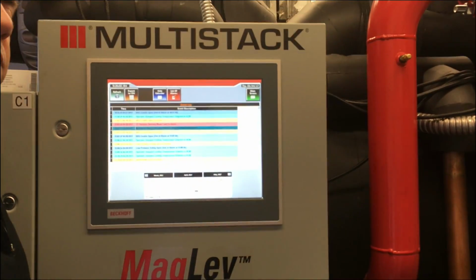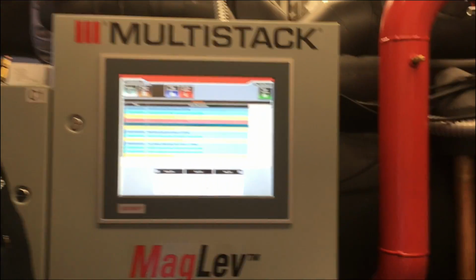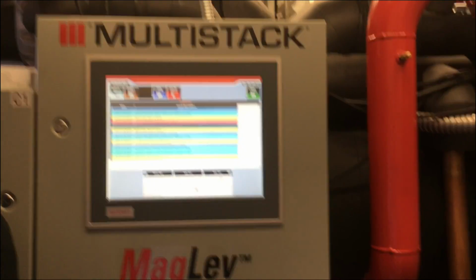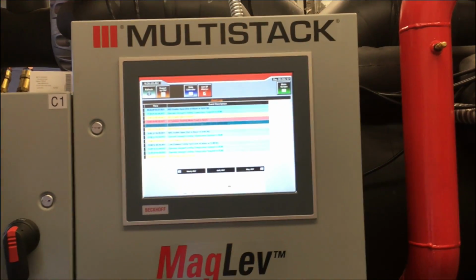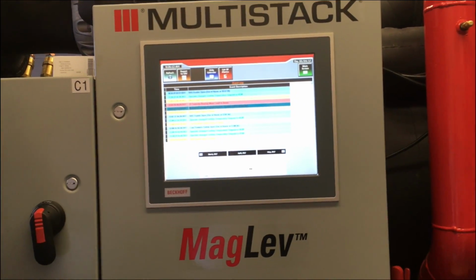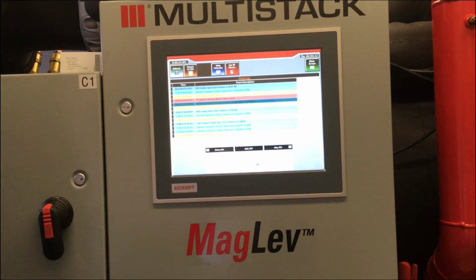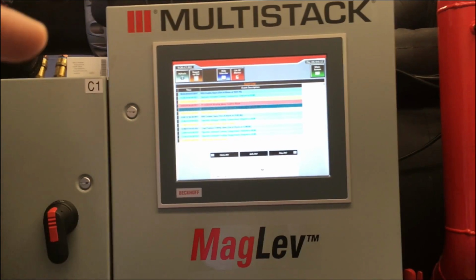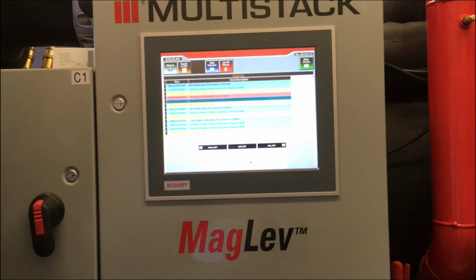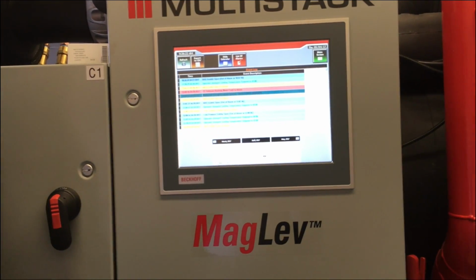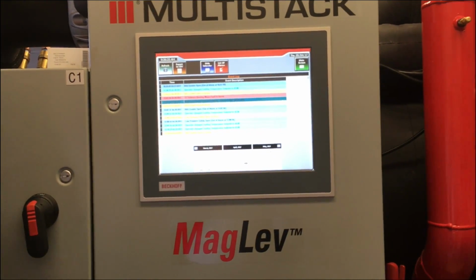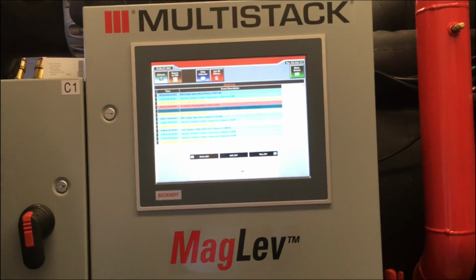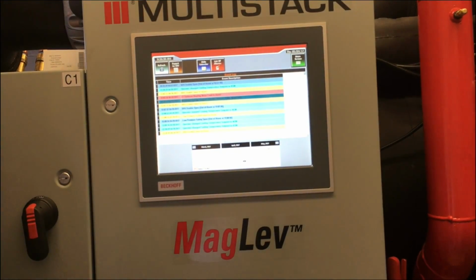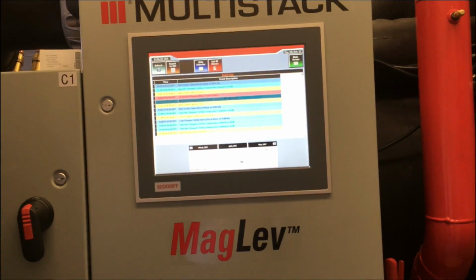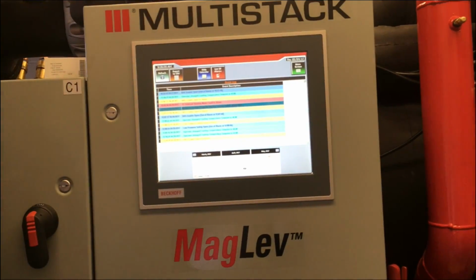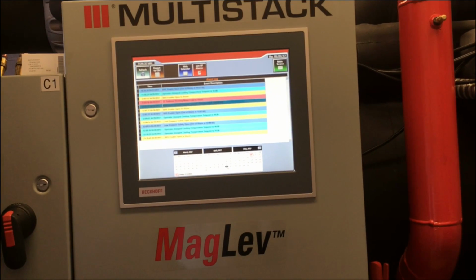6 o'clock at night? No, the problem was that on EMS, the set point over there for the chiller went to 0, but here on the machine it was still 45. We couldn't understand why we were seeing 0, so we called ATCO, and they said, okay, just cycle power. So when they came in and cycled power, that's what you're seeing. Yep, and that went to 0 over there.